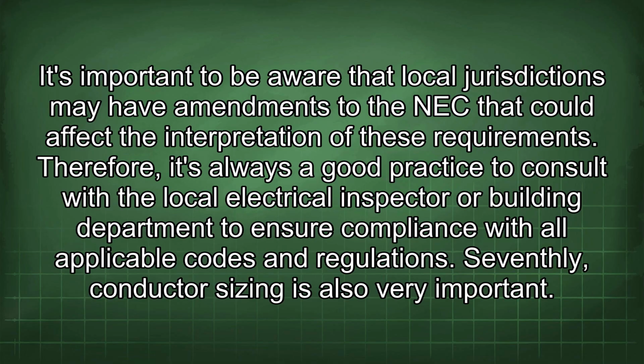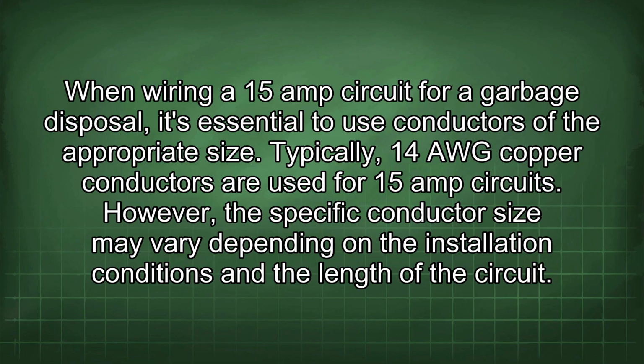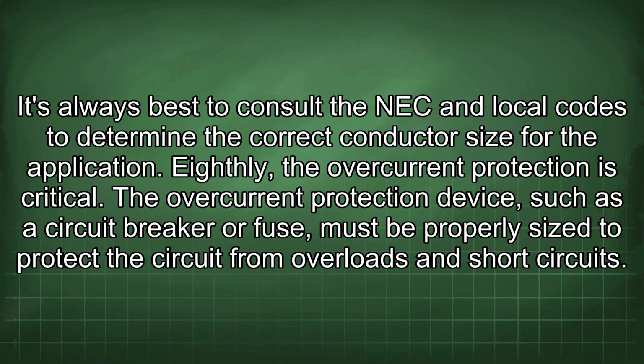Seventhly, conductor sizing is also very important. When wiring a 15-amp circuit for a garbage disposal, it's essential to use conductors of the appropriate size. Typically, 14 AWG copper conductors are used for 15-amp circuits. However, the specific conductor size may vary depending on the installation conditions and the length of the circuit. It's always best to consult the NEC and local codes to determine the correct conductor size for the application.